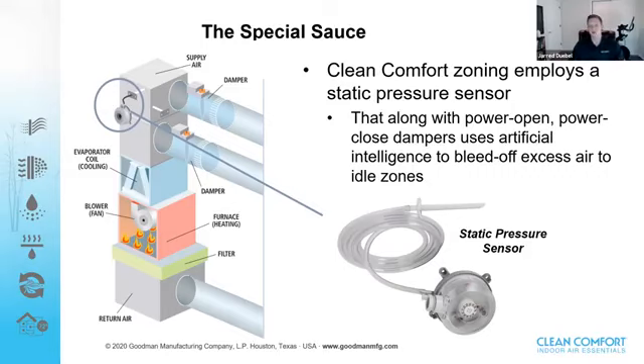So the way it works, let's go back and say our 3-zone system. Let's say zone 1 calls and zones 2 and 3 are satisfied, so they're closing. Again, like the example Jonathan gave earlier, zone 1's open. We're pushing a lot of air into that specific zone, zones 2 and 3 dampers are closing, and static pressure increases. It's just like putting your thumb over that garden hose. We're pushing all that air in one specific area, and then we could reach that static pressure threshold.